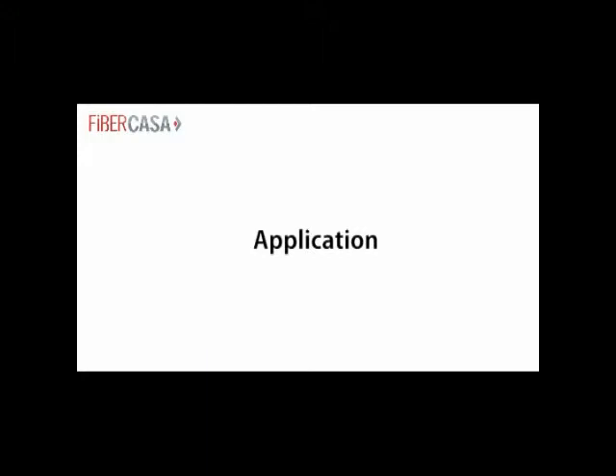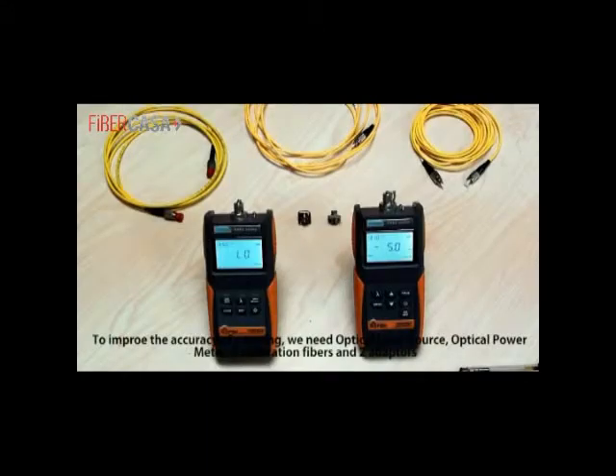Application. To improve the accuracy of a testing, we need optical laser source, optical power meter, two calibration fibers, and two adapters.